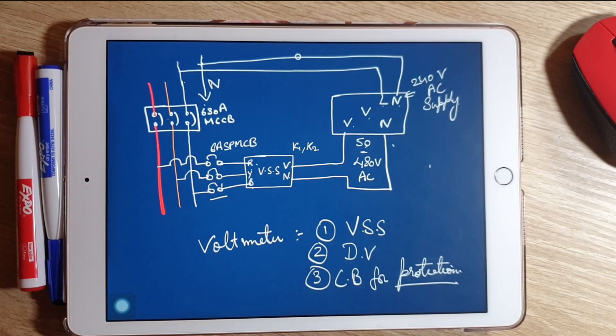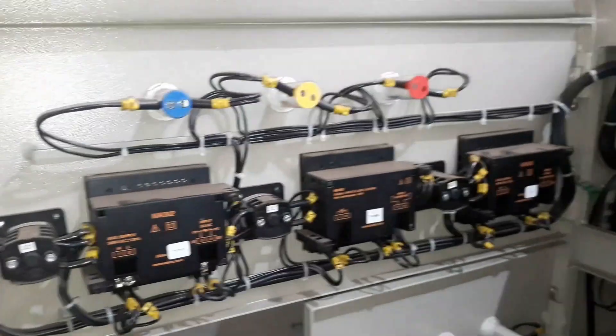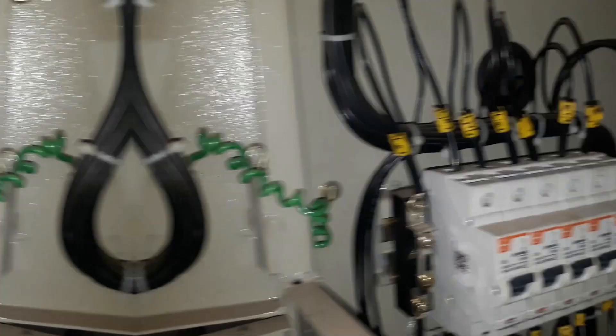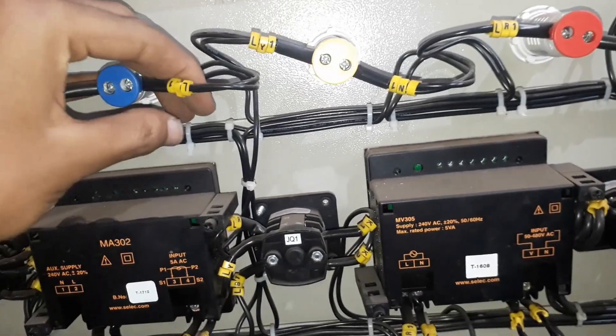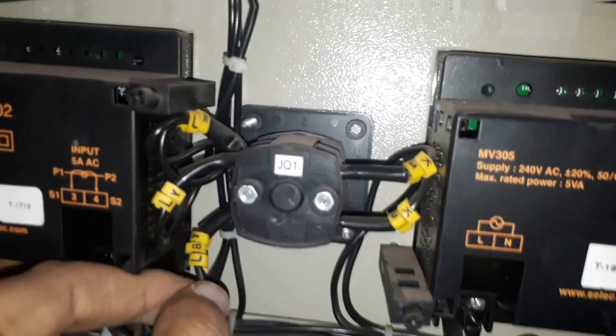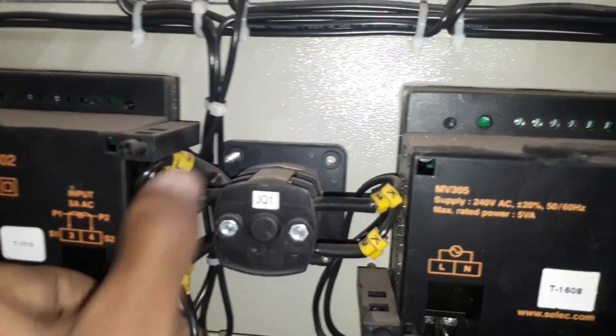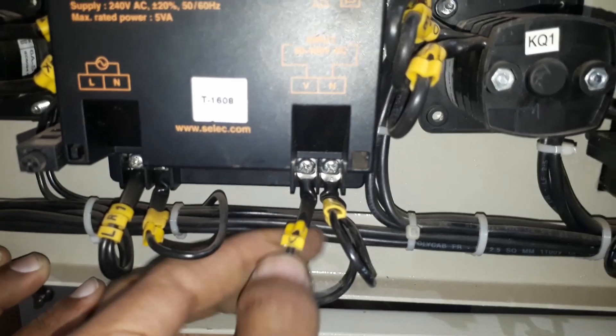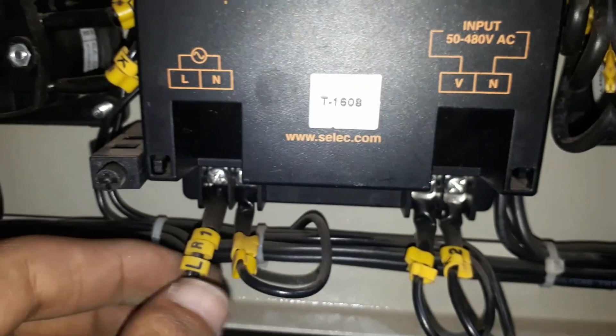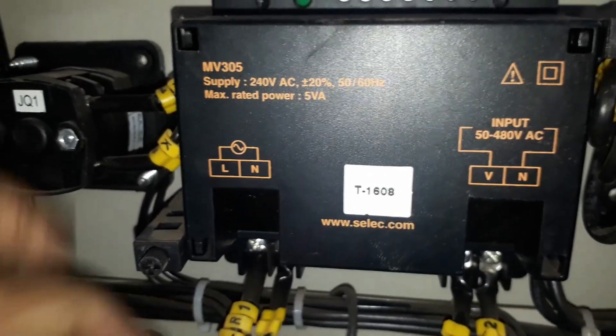Practicing this wiring practically — I am using three 6-ampere single-pole MCBs for R, Y, B and connecting them to three indicators for R, Y, B indication. The three phases are looped from these indicators and connected to the R, Y, B terminals of the voltmeter selector switch. The K1 and K2 terminals are connected to the V-N terminal of the voltmeter for 50 to 480 volts AC, and a single-phase auxiliary supply is connected.